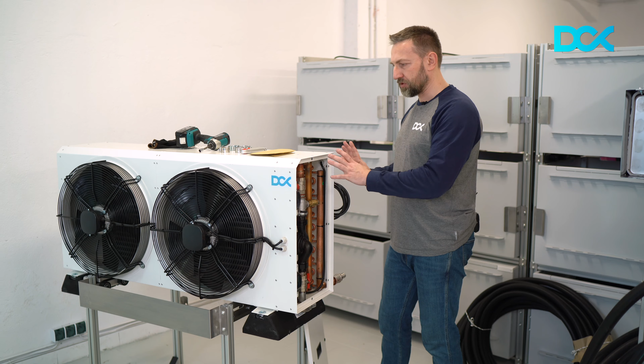But with that unit, it may also run in the very uncommon but hot ambient air of 50 degrees or even more, because it's cooled by the same dry cooler which is cooling your system. So the pump has the capacity of 160 liters per minute. It's already preset on speed three, so it works already on the maximum capacity.